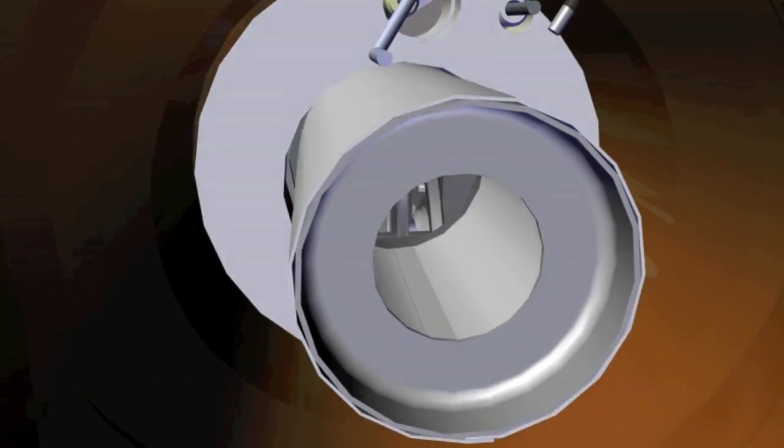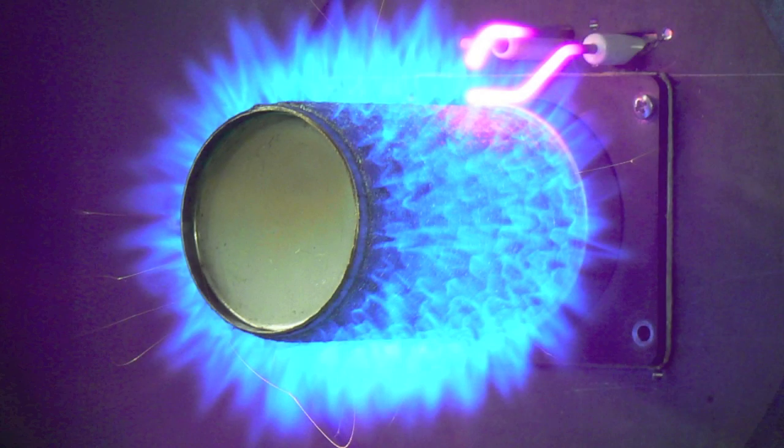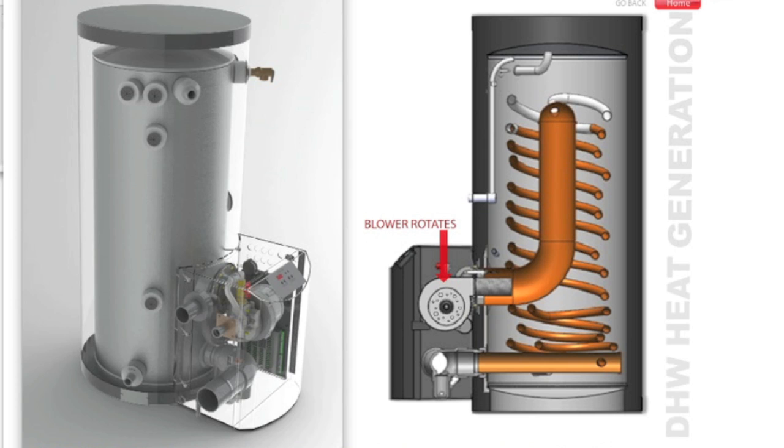These unique flue gas channels carry supercharged heat in excess of 2,000 degrees Fahrenheit from the burner up the 5-inch diameter combustion channel and back down the spiraling tubes that transfer heat to the water surrounding each tube to produce very efficient heat transfer to the water.